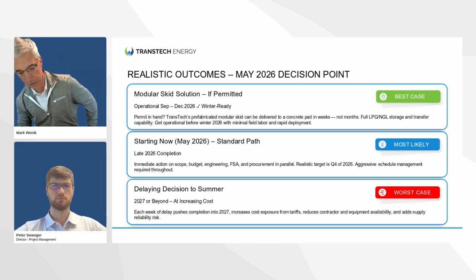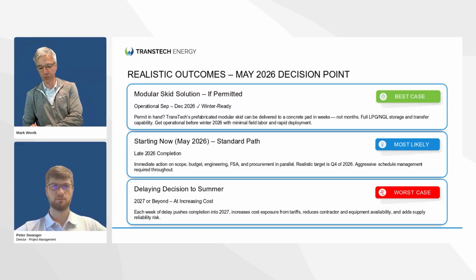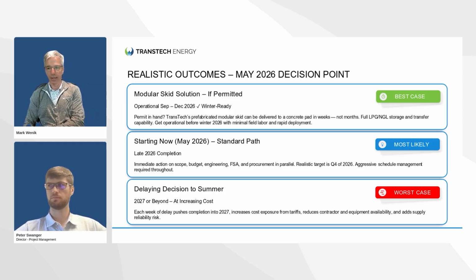Thanks, Peter. I wanted to add two points to the commissioning piece. First, our crews make sure your team is trained on the operation of the facility, and in some cases we'll bring in first responders and walk them through it, showing where the emergency shutoff valves are, how everything operates, why the relief valves are there, and where the correct position is for emergency shutoff stations. The other piece is making sure that bobtails or transports filling can unload properly.